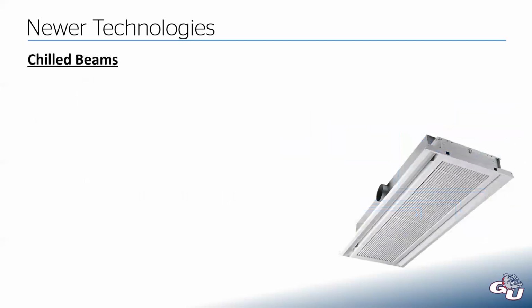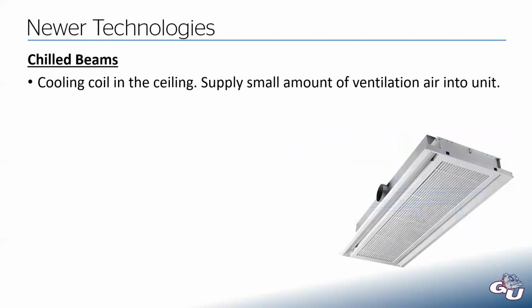And then we have chilled beams. So what a chilled beam is essentially a chilled water cooling coil that hangs up in your ceiling. So you can imagine this sitting in the ceiling with some ceiling tiles surrounding it to give it a nice flush look. So we're going to supply a small amount of ventilation air into this unit. That would be this collar right here. So we would duct up a DOAS ventilation unit and push some ventilation into the coil right there.